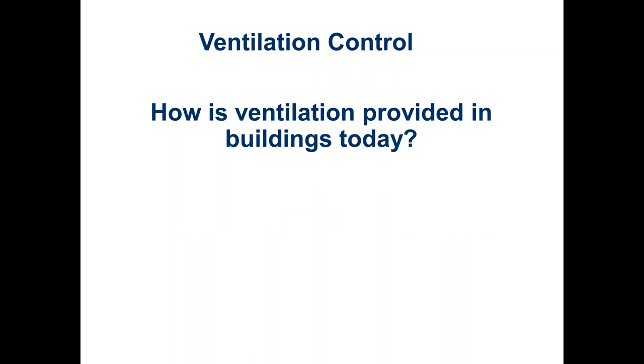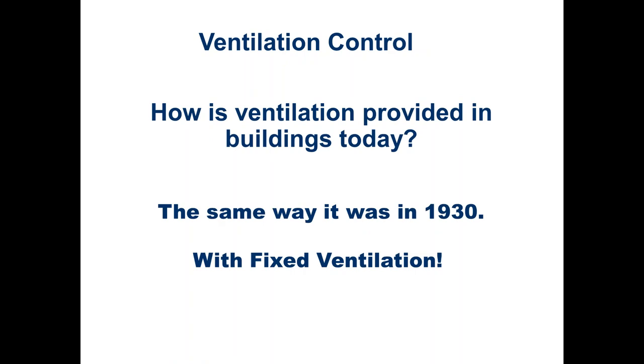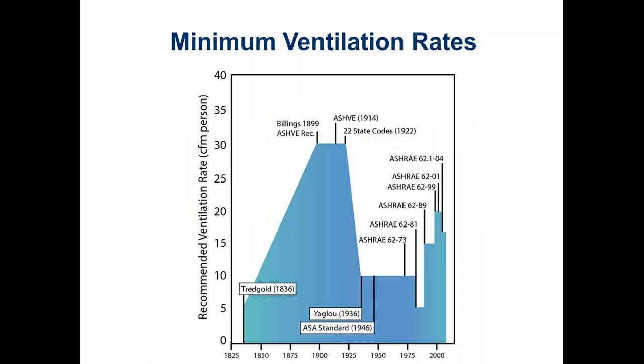How is ventilation provided in buildings today? Basically, it's provided the same way it's always been. Someone dictates a fixed amount of outside air we have to bring in, generally dictated by mechanical or ventilation codes. We bring in that fixed amount of air. But all that fixed ventilation is based on the building being occupied at the maximum, which it seldom is. So there's a lot of waste involved, and CO2-based demand control ventilation is specifically designed to reduce that overventilation waste.